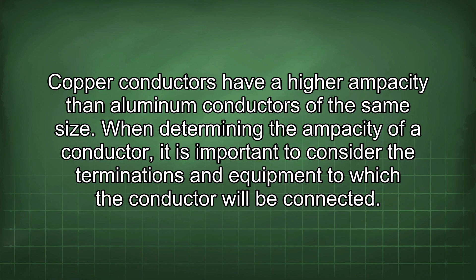When determining the ampacity of a conductor, it is important to consider the terminations and equipment to which the conductor will be connected. Terminations and equipment are often rated for a specific temperature, and the conductor ampacity must be selected so that the temperature rating of the terminations and equipment is not exceeded.